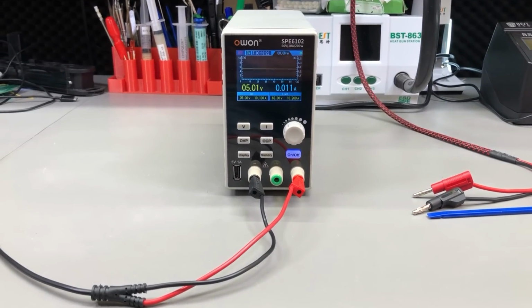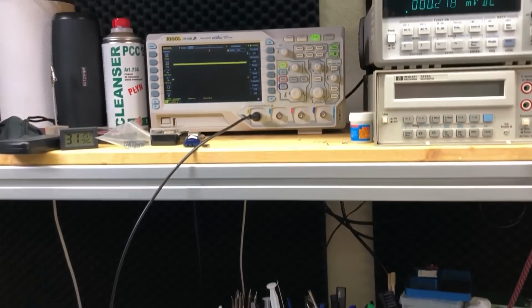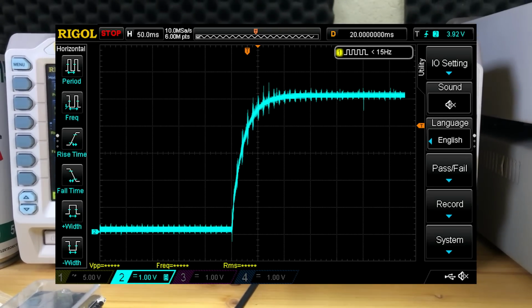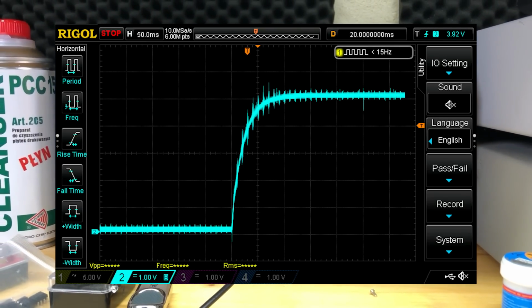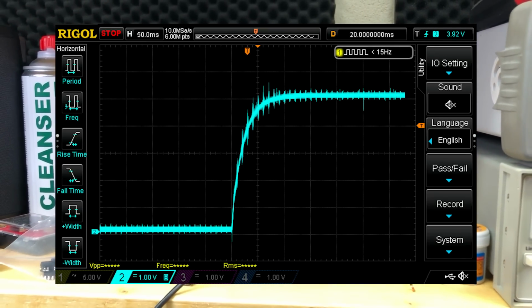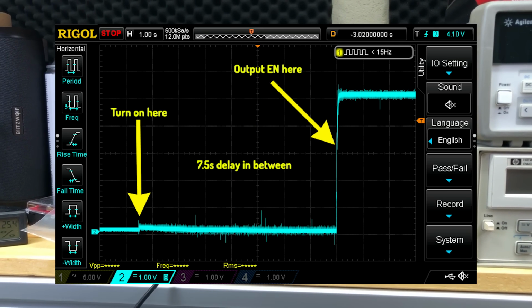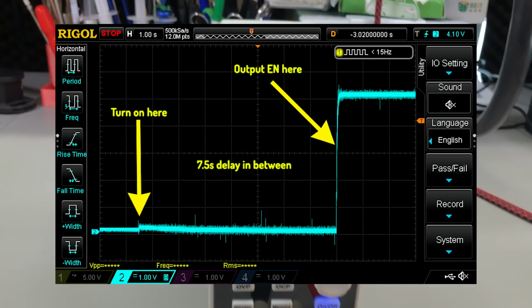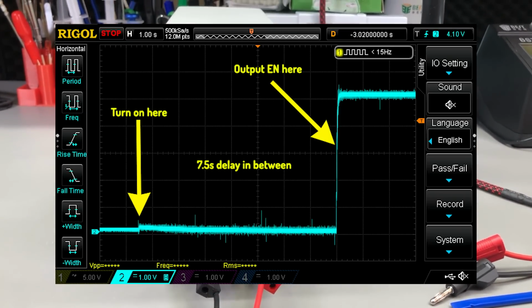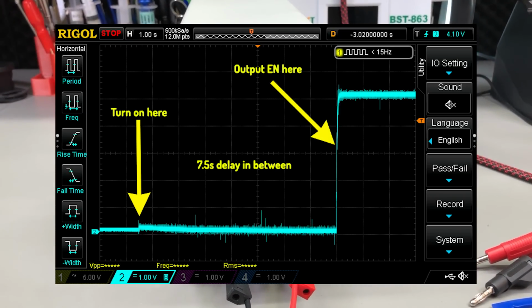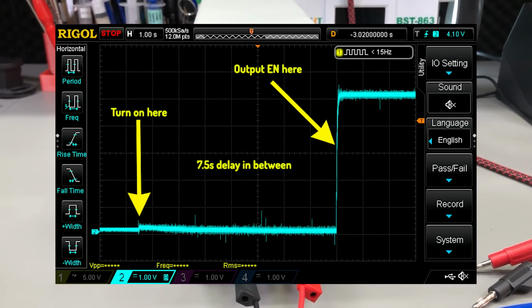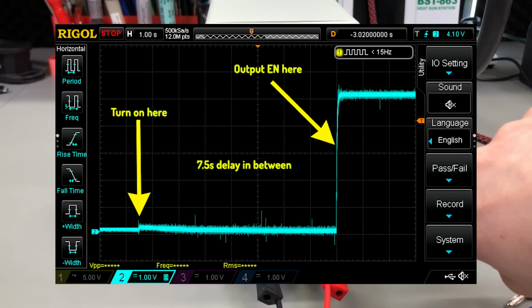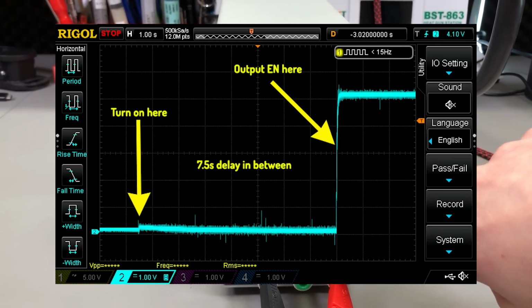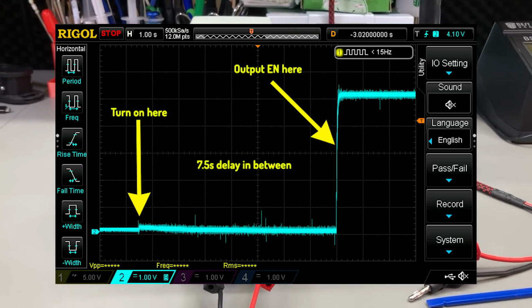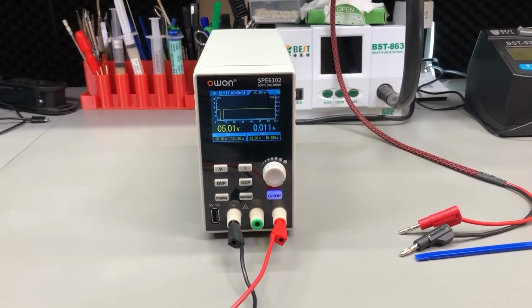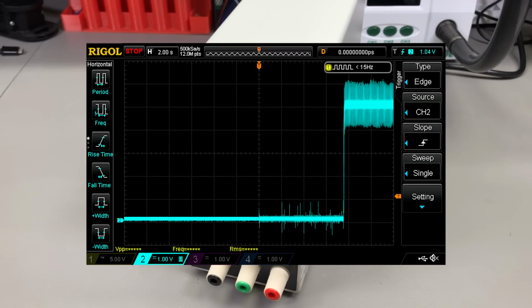Next up, I tested for voltage or current overshoot in various scenarios. Here is the test for voltage overshoot with no load. This is soft key turn on, and there is no voltage overshoot here. And hard power switch turn on, again, no voltage overshoot. They do have this 7.5-second delay from the moment you start the power supply until it automatically enables the output. So they are waiting for the PSU to be up and stable before enabling the output. But as a side note, this waveform is not clean. Look at the amount of noise we have in there. I've also tested with an 8 ohm load, about 0.6 amps.